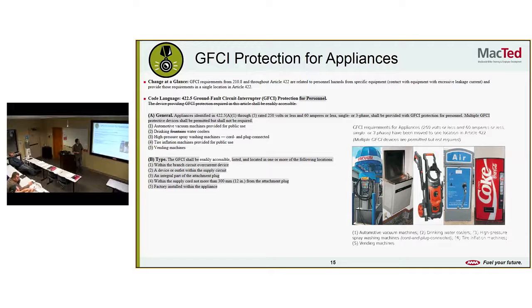And there's a B, so the type: GFCI shall be readily accessible, listed, and located in one or more of the following locations. Within the branch circuit overcurrent protective device, so it could be built into the breaker. Device or outlet within the supply circuit, so outlet, like it said. An integral part of the attachment plug, so that's your whip. Within the supply cord, not more than 12 inches from the attachment plug, like the ones that we have, the plug-in inline, you've all seen those. Factory installed within the appliance, so it can be built into the appliance too. So GFIs are just continuing to add more and more requirements for them. Makes sense.